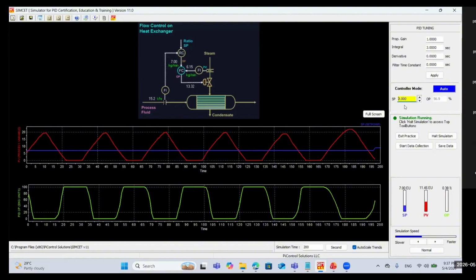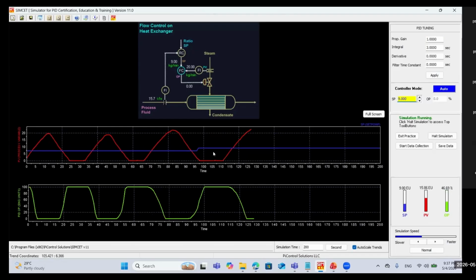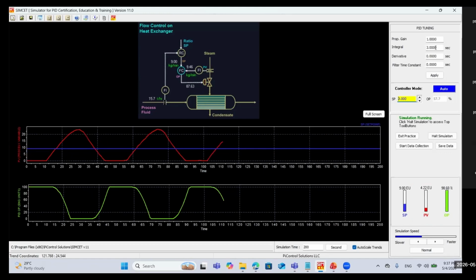From the previous slide I showed you, these are consistent and frequent oscillations. It is never settling down. It's never settling on the set point. So it is an indication that I'm having a high proportional gain. I can decrease it, make it 1, apply, and do a step change. Again, it's oscillating. So again, I will have to decrease the proportional gain. It's 0.5.